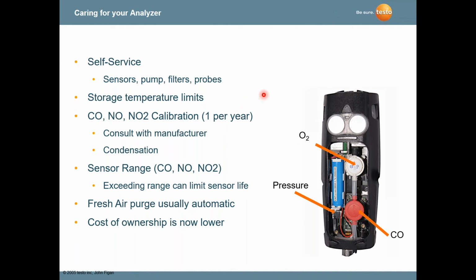The calibration of the CO sensor is typically once a year, where we put a known concentration of CO on the sensor, and it has to be within specs, which is plus or minus 5 ppm. Oxygen, on the other hand, every time you turn the instrument on, we're calibrating the O2 cell to fresh air, 21%. We're trying to lower the cost of ownership of these analyzers.